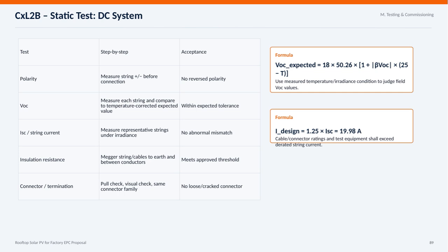Then we measure the short circuit current, or ISC, for representative strings under irradiation to detect any abnormal mismatches that might indicate faults or shading issues. For insulation resistance, we use a megger to test the strings and cables to earth and between conductors, making sure the resistance meets the approved minimum threshold to avoid leakage currents or hazards. Finally, connector and termination tests include visual and pull checks, verifying that connectors are from the same family and show no signs of looseness or cracks.